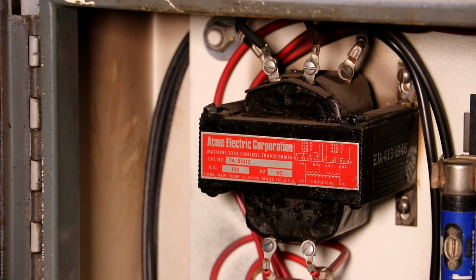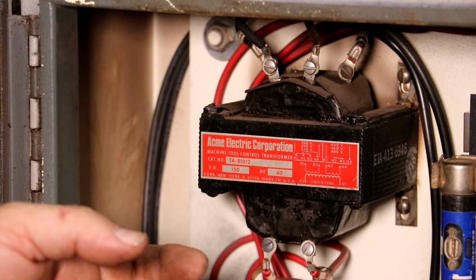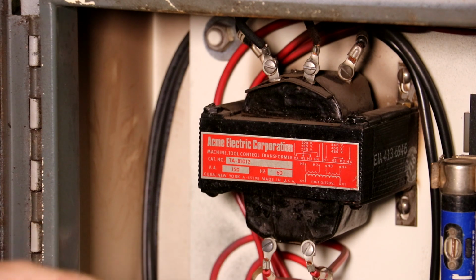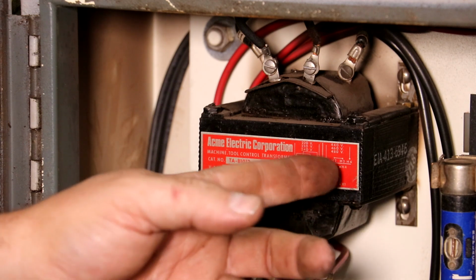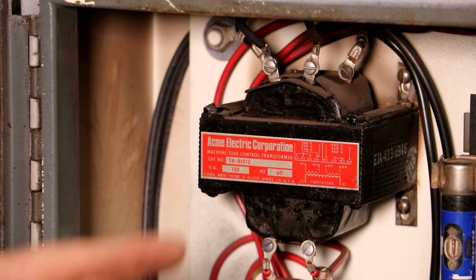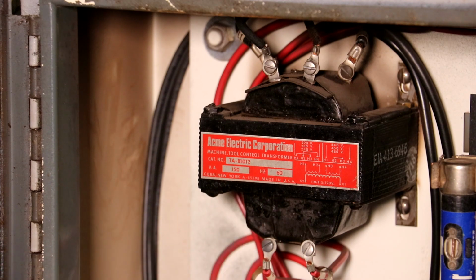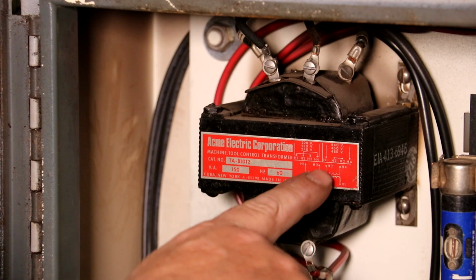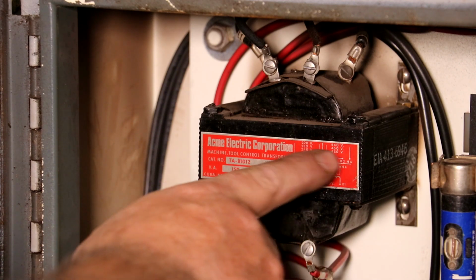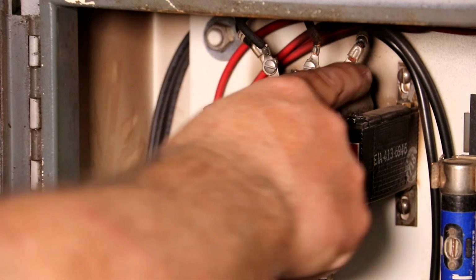We often talk about 220, 230, 240 - yes, they're different voltages, but most motors and systems can work in between those ranges. I think mine is actually on 220. In a more commercial setting it'd probably be like 240, or going to the 400 volt range would be 480. Anyway, I digress - but if you look here, for the high voltage option there's 4 terminals on top, 1, 2, 3, 4.